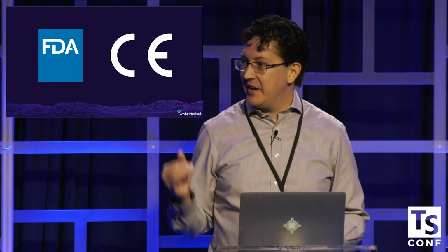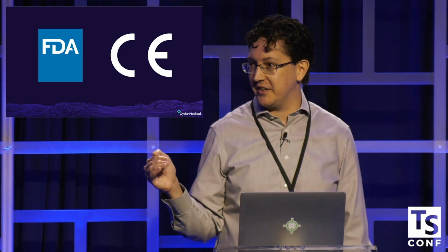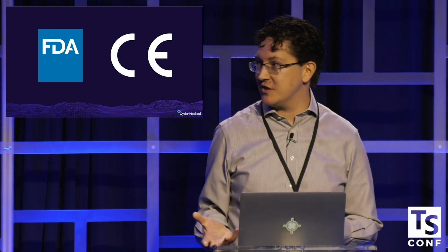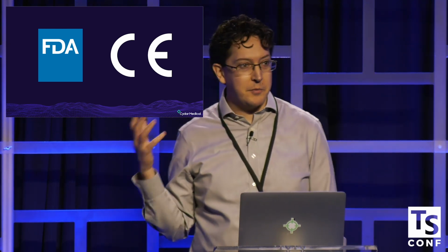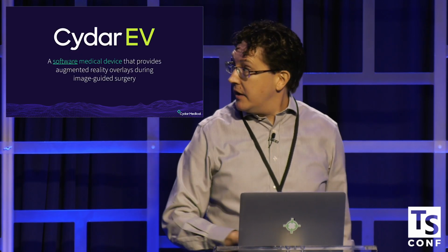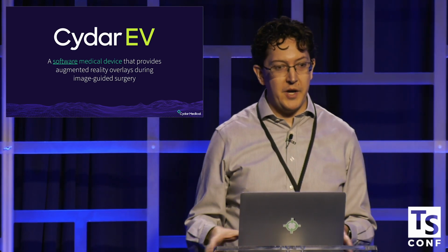For example, is this change to fix a security flaw? Then essentially, you don't need a new 510K. If you are making a change to fix a security issue, they say, get that out. That is something that you can do. So the regulatory agencies are becoming far more aware of software as a medical device. But the key is we want it to be just the software, not the hardware.